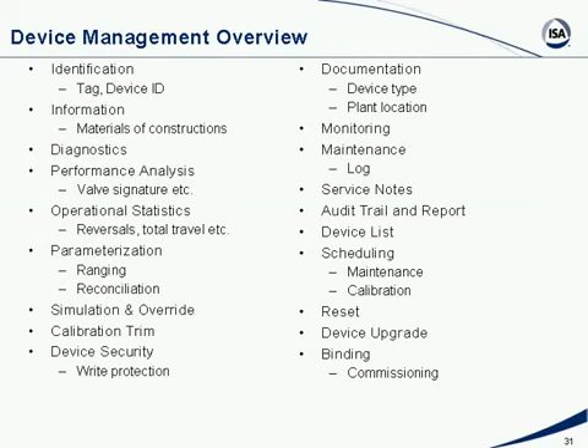I have live diagnostics from the device. I have the ability to do performance analysis, capture valve signature and step response, to see the health of my valves. Operational statistics, you know, valve positioners commonly count the reversals and the total travel, which is of course an estimate of the wear and tear on the valve, which are then used for predictive maintenance.